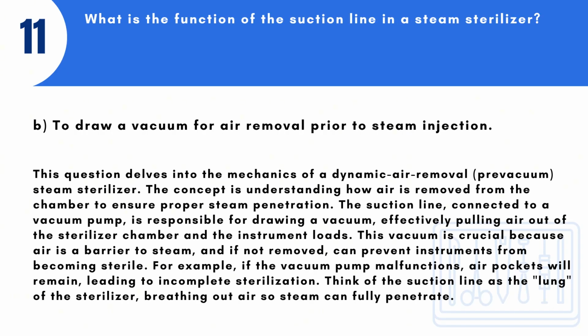Answer: B. To draw a vacuum for air removal prior to steam injection. This question delves into the mechanics of a dynamic air removal, pre-vacuum, steam sterilizer. The concept is understanding how air is removed from the chamber to ensure proper steam penetration. The suction line, connected to a vacuum pump, is responsible for drawing a vacuum, effectively pulling air out of the sterilizer chamber and the instrument loads.